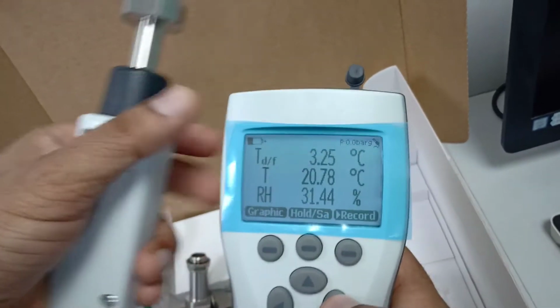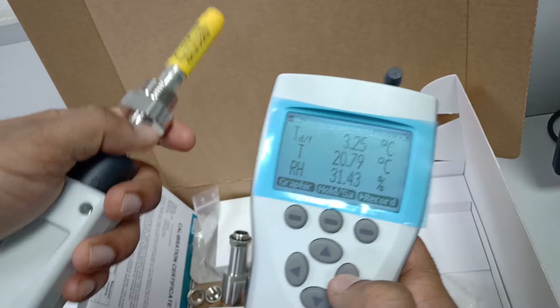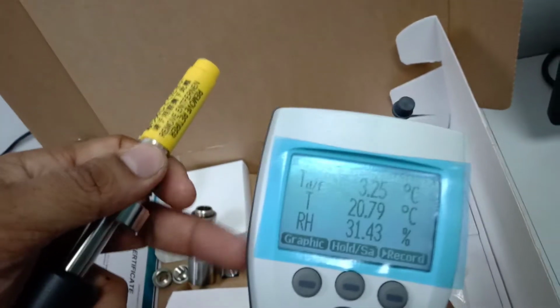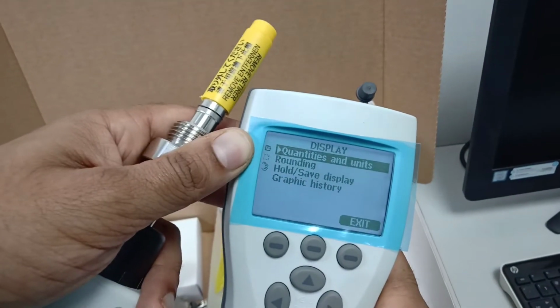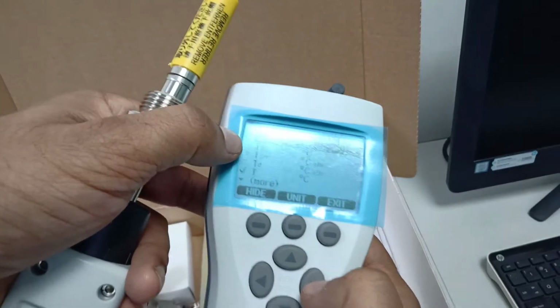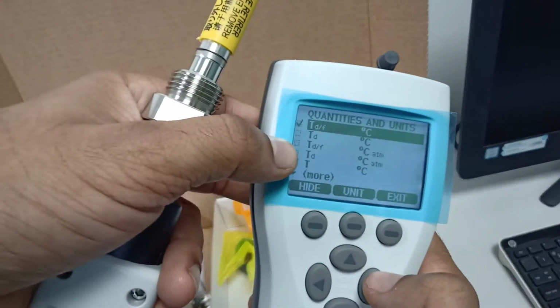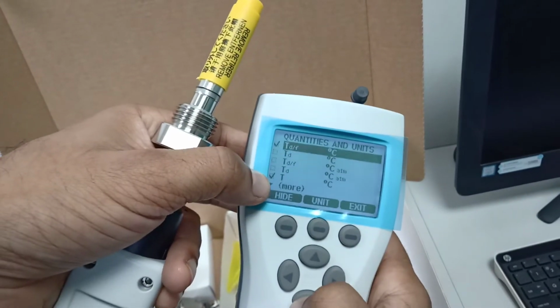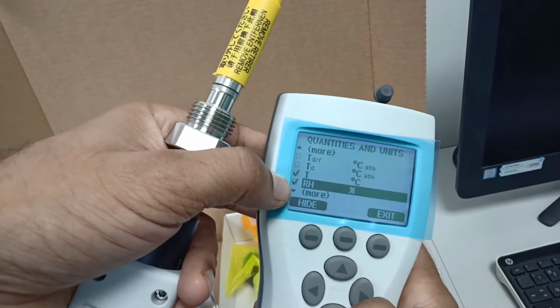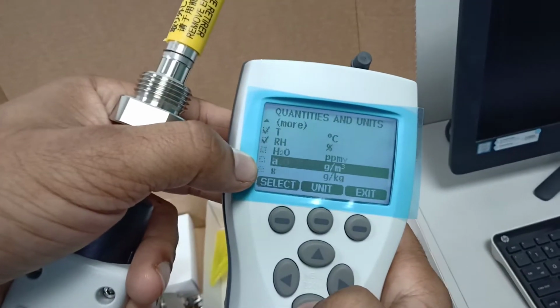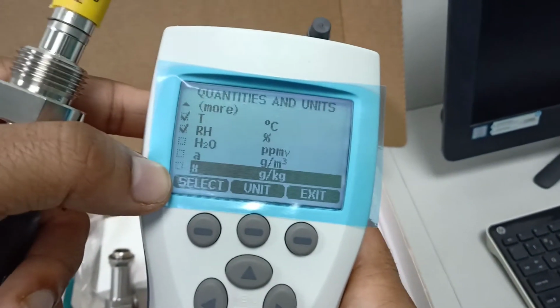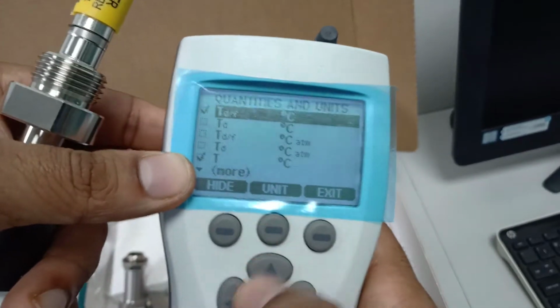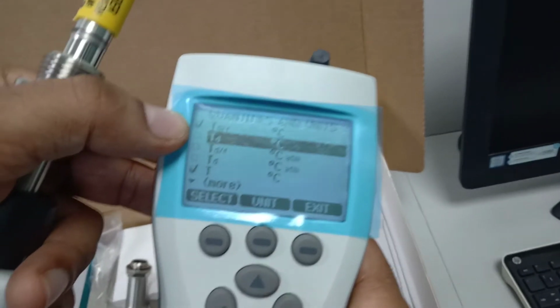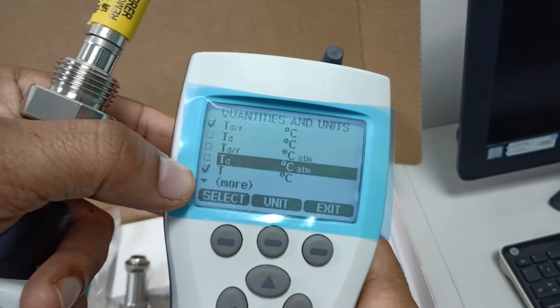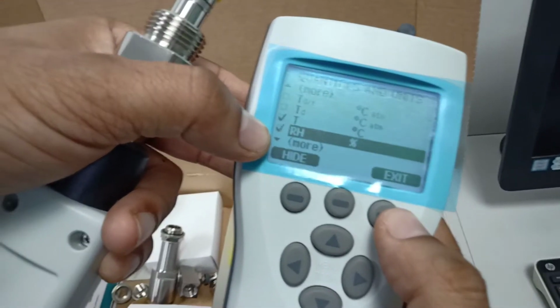So, and now say Vaisala SF6 dew point kit. This has many parameters. So you can measure dew point, frost point. You can measure other parameters as well. So quantities and units: dew point, frost point, dew point only, dew point, frost point in terms of atmospheric pressure, temperature, relative humidity in terms of ppm, and these are other parameters: mixing ratio, absolute humidity. So at a time you can select any three parameters. So for now I am selecting the dew frost point, temperature, and relative humidity. I exit.